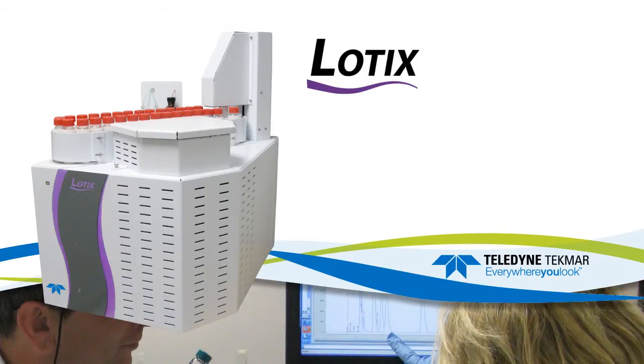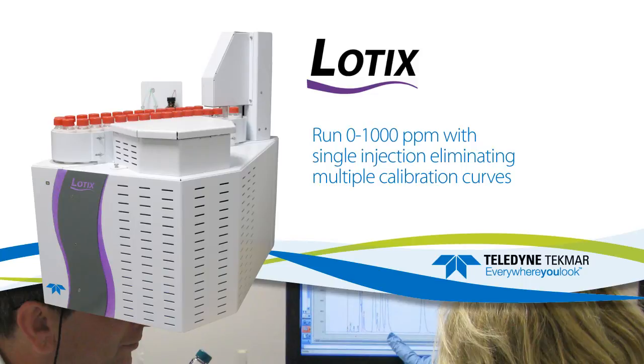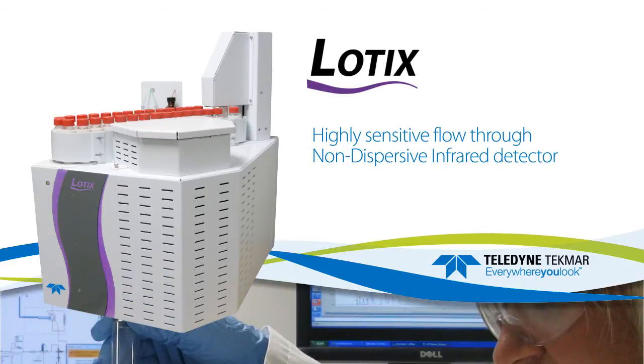The Lotix TOC Analyzer features no syringe drives or seven port valves, the ability to run zero to one thousand parts per million with a single 0.5 milliliter injection volume, virtually eliminating the need for multiple calibration curves, and a totally new and highly sensitive flow-through NDIR detector.